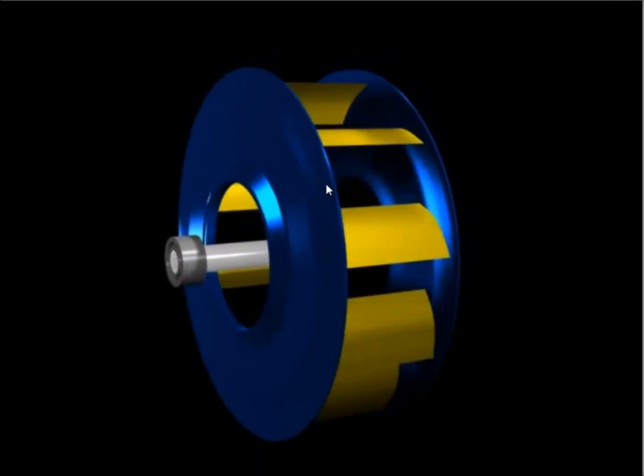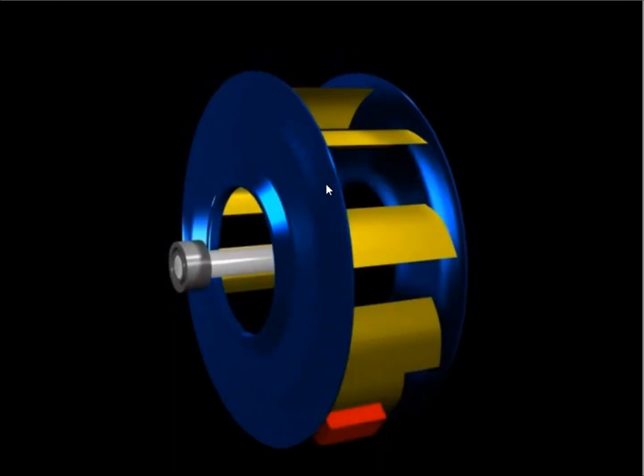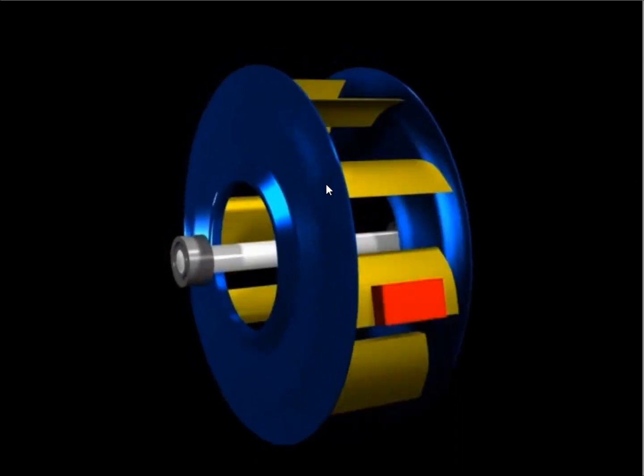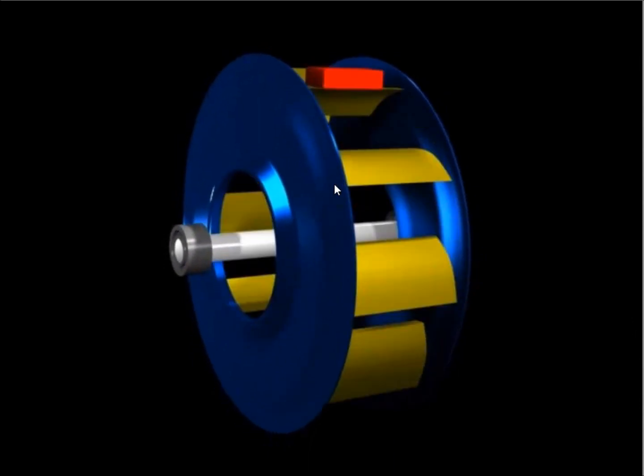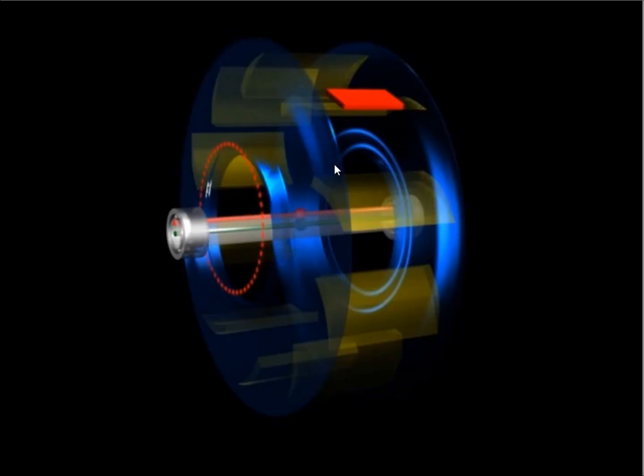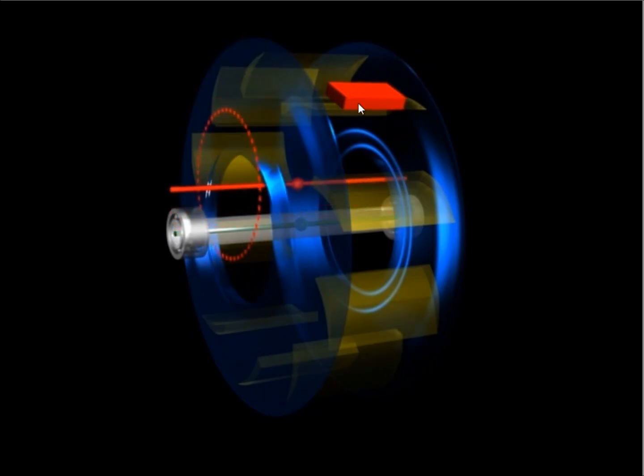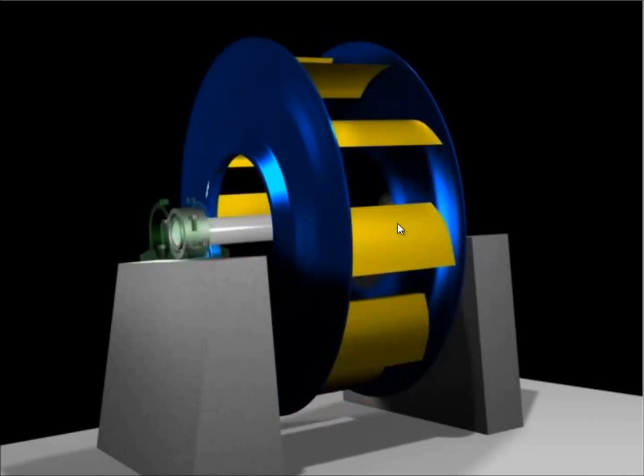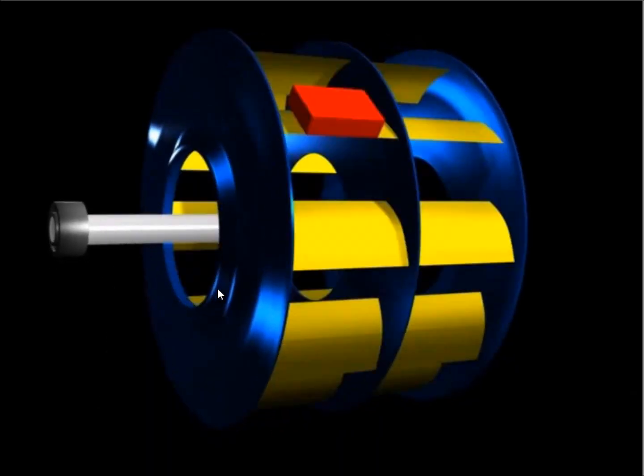The most common type of unbalance with narrow rotors is called static unbalance — that's where all the unbalance is more or less in a single plane. We can see the characteristic motion of static unbalance: the center of mass is moved away from the center of geometry. As the out-of-balance mass is increased, the center of mass is pulled further from the center of geometry. When we run the machine, we mount it in bearings, and those bearings are trying to contain those circular forces.